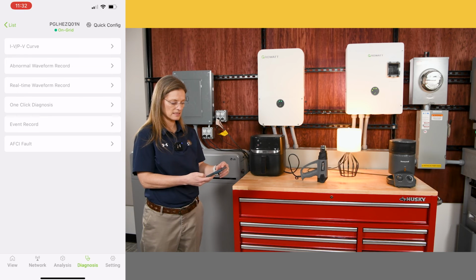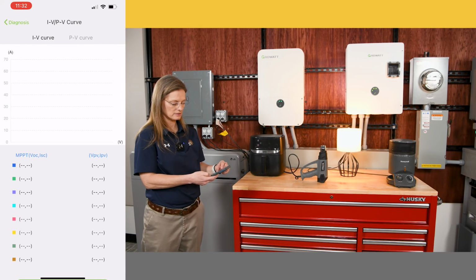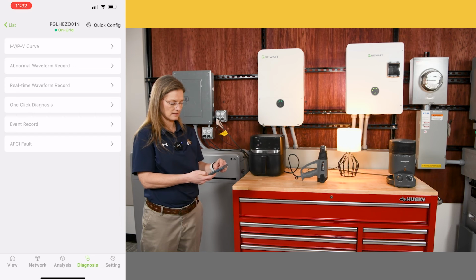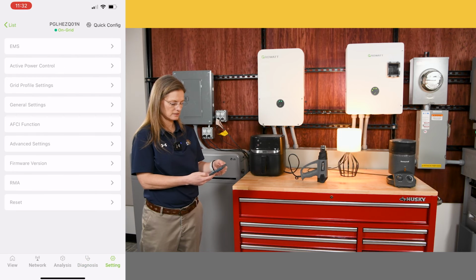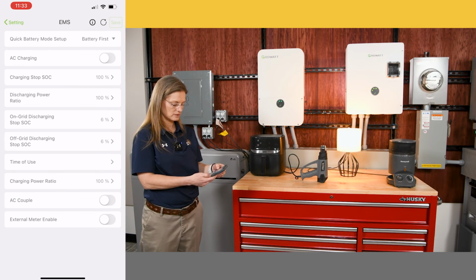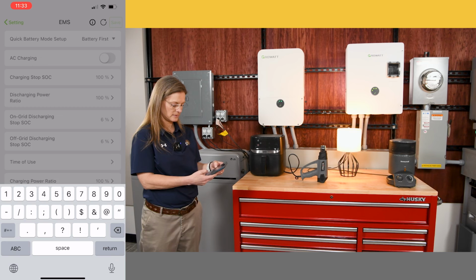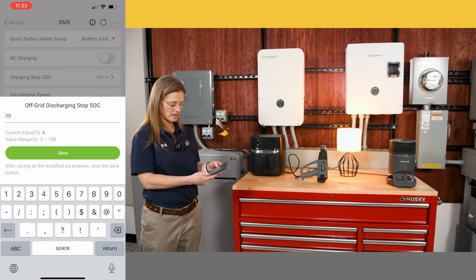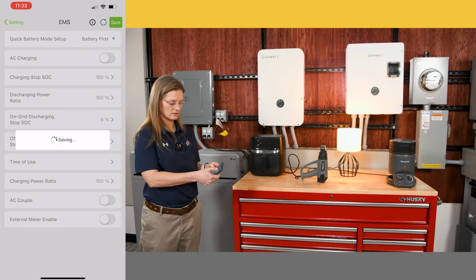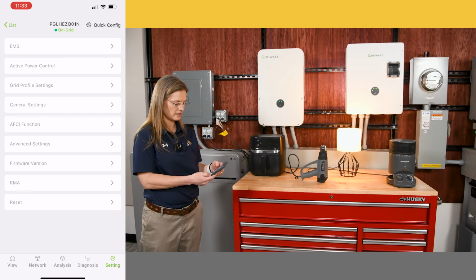We can see diagnosis. There's a neat IV PV curve. If you have PV connected there, you can see how much power and voltage you're getting from your PV. And different information there. If you have any arc fault current interrupters there, you can see that. We'll go back to our settings, and here's a quick list of all of your settings. If you wanted to set up anything for time of use, you could do that here. If you wanted to set up your on-grid discharging, stop SOC or off-grid discharging, we might change that here to say stop discharging our batteries at 20% and save that there. You could change that there. So we'll say save.